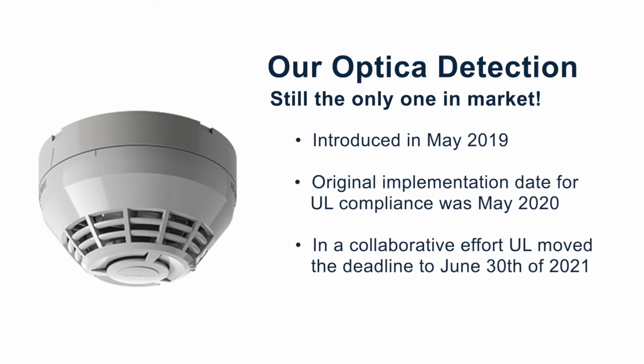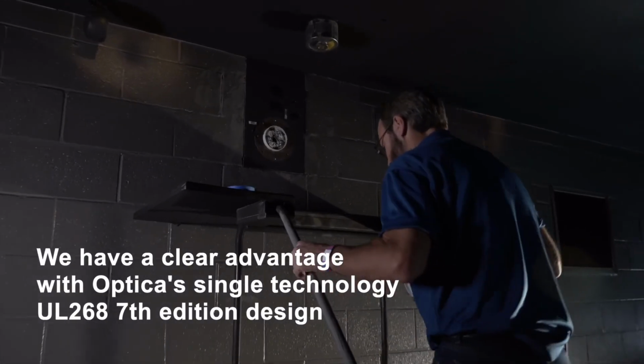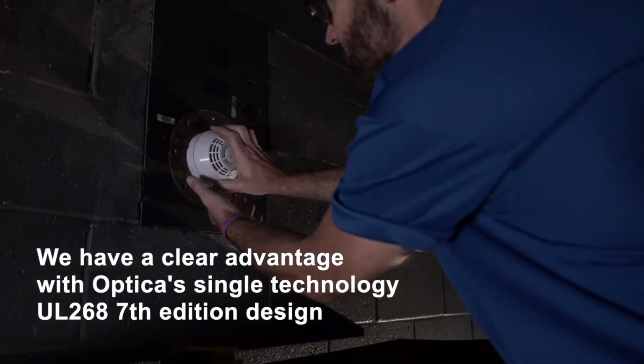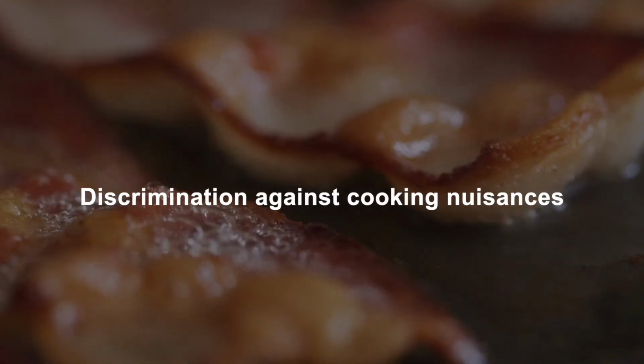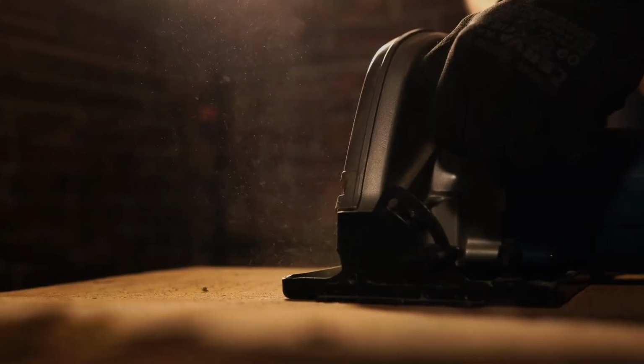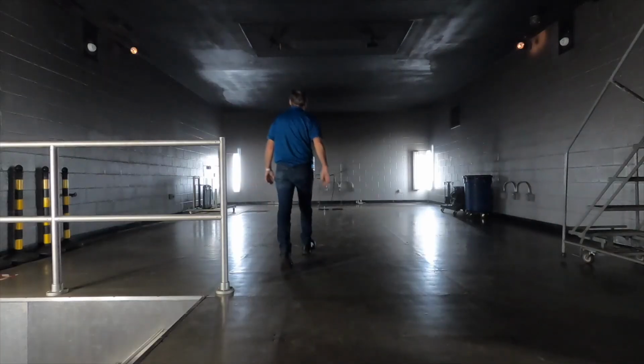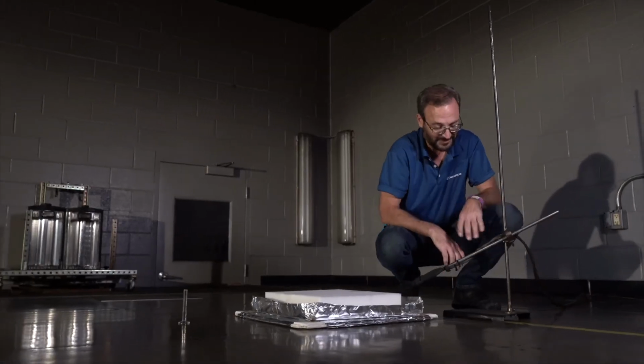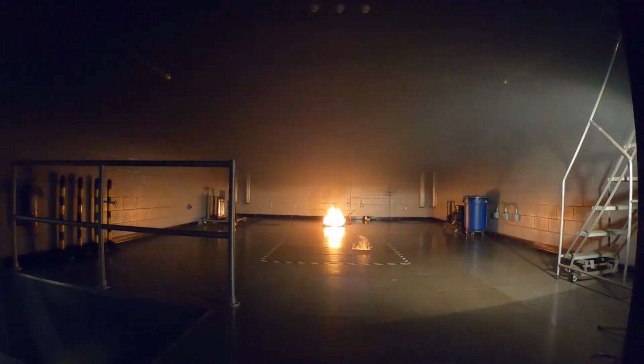But because so many manufacturers were having to test, redesign, and then retest, UL, in a collaborative effort, moved the date to June 30th of this year. And as expected, other manufacturers are finishing their agency approvals and making these products available to their customer base. As I've stressed in conferences, webinars, roadshows, we have a clear advantage with Optica with a single technology UL 268 7th edition design, which includes discrimination against cooking nuisances, but also other non-fire sources that would put standard single technology smoke detector into alarm. That capability, combined with its faster response to fires, gives us a clear advantage in specifications against competitors trying to pass the new tests.